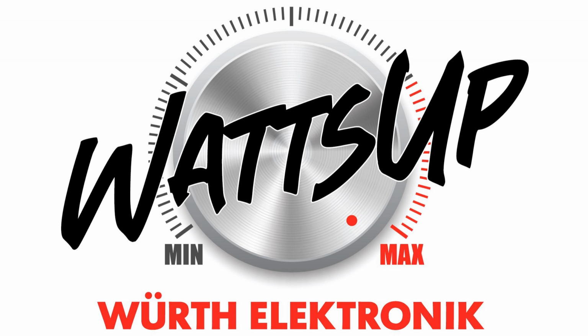And the last main parameter I would like to mention is the insulation test voltage, which of course is related to the rated voltage. So also there's a factor between them given in the standards. For this component, for example, it's 3 kilovolts RMS. An AC voltage is applied with a frequency of 50 Hertz, and over a period of 2 seconds, the current is monitored, and it should not go above 5 milliamps in this case.